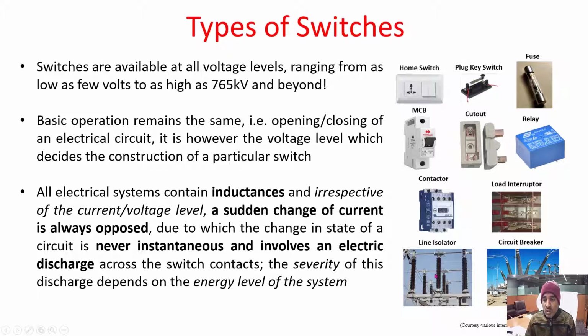But all switches are not capable like a circuit breaker, which as per the definition you have just seen does making, breaking and carrying. Now, switches are available at all voltage levels, ranging from as low as a few volts to as high as 765 kV and beyond. The highest rating is equal to the highest line voltage. Now a 1200 kV line has come up in India, so there must be a circuit breaker associated with that, obviously. So this is how switches are available at all voltage ratings.